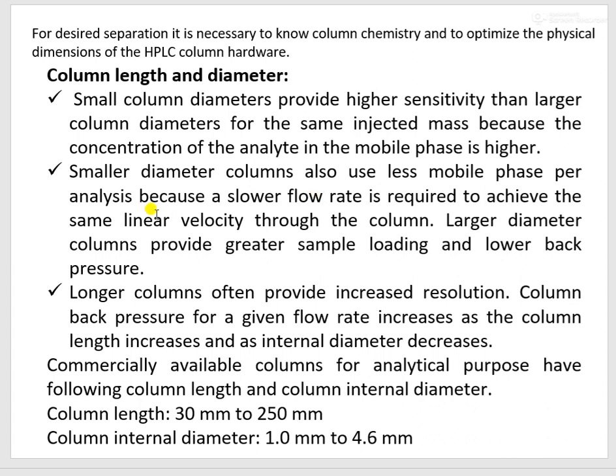Large columns provide greater sample loading and lower back pressure. The stationary phase contained within a large diameter column will be more compared to a small diameter column, hence you can load more sample to a large diameter column. There will also be less back pressure with a large diameter column. Coming to column length — longer columns often provide increased resolution. Column back pressure for a given flow rate increases as column length increases and internal diameter decreases.